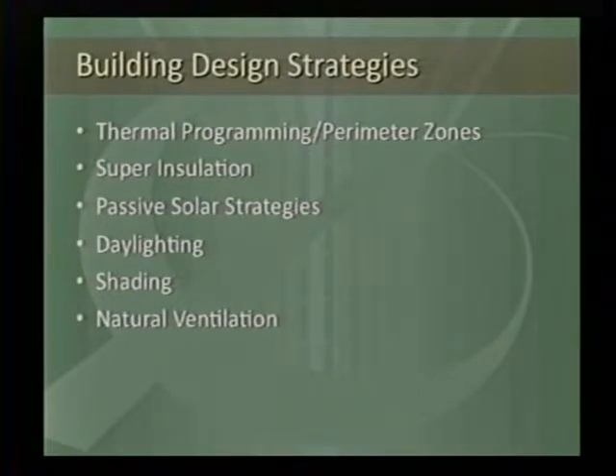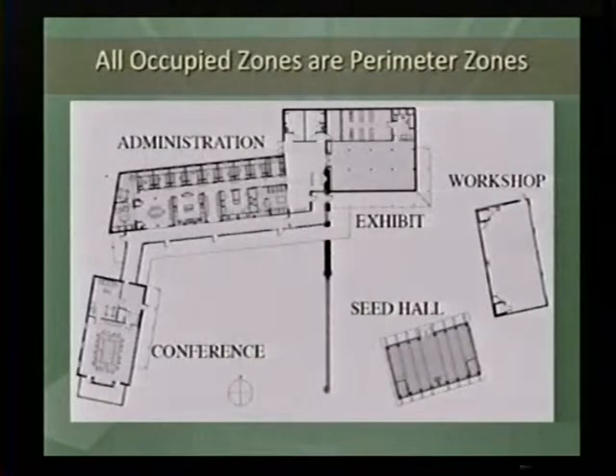We set up at that meeting a series of building and design strategies, the kind of things that we thought about since we had everyone there as a group in a sort of brainstorming notion to work at. And I'm dividing these strategies, even though they were discussed at that particular meeting, into building design or shell strategies and HVAC strategies. I'll go through them quickly. One of the building design strategies that is, I think, less talked about and really very interesting is all of the issues that you deal with when you're programming the spaces. If you want to do a building that's going to be naturally ventilated, and you would like to be able to turn down the HVAC equipment or turn it off when you're naturally ventilating, the same way you would turn your air conditioning off in your house when you open windows, then all of the occupied spaces need to be perimeter spaces so they have access to that natural ventilation.